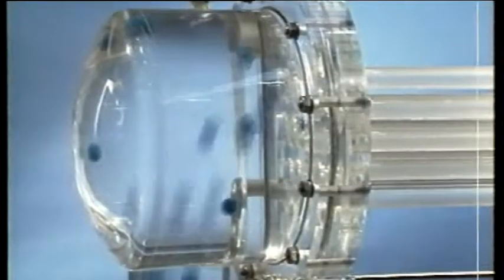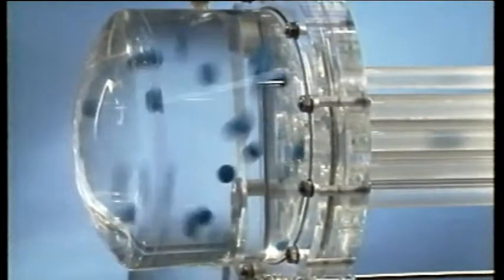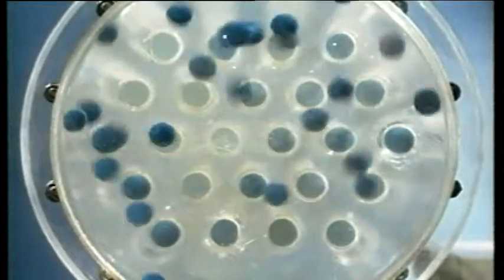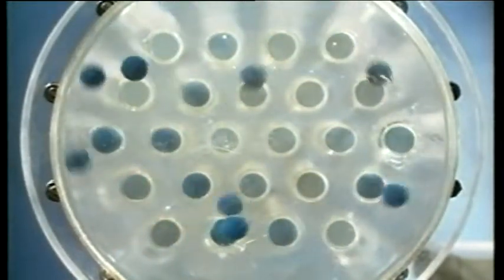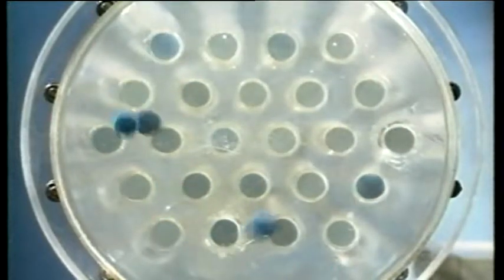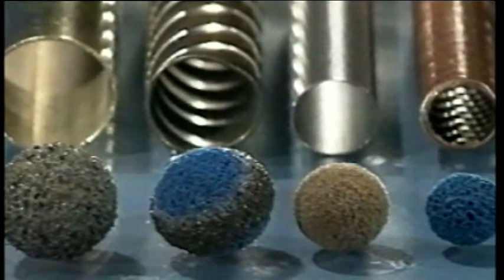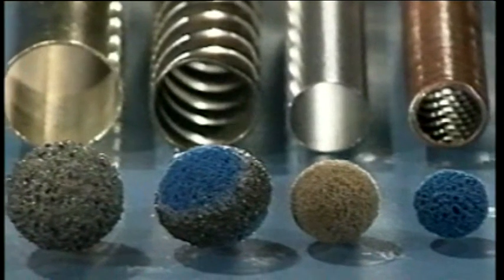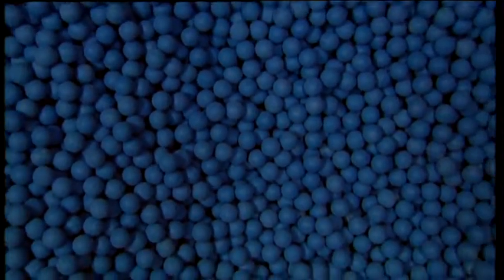The cleaning balls are injected into the cooling circuit directly upstream of the condenser and distributed evenly across the entire tube sheet. In this way, every individual tube is cleaned and the best possible heat transfer maintained in the long run. This means less fuel input. In power stations alone, existing Taprogge systems help to save fuel in the amount of 20 million tons hard coal units every year. Every power station condenser, every desalination unit evaporator, every tubular heat exchanger, no matter how small, can be cleaned by the Taprogge system.